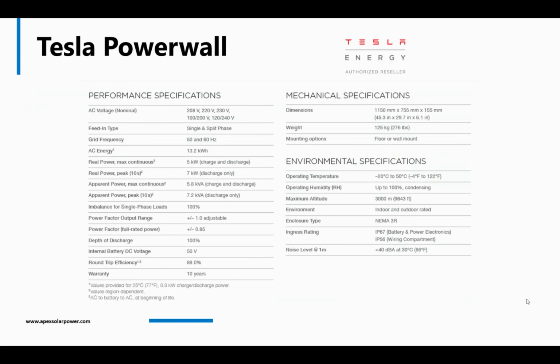The Tesla Powerwall is really meant for inside mounting or installation. If you were in California or Hawaii, outdoors would be fine. Lithium ion works best at about north of 50, 55, 60 degrees - somewhere in that range you're going to get optimal performance. Its operating temperature is listed as minus 4 Fahrenheit to 122. Yes, it'll operate at those temperatures, but not at peak performance. Peak performance for lithium ion is north of 60 degrees.